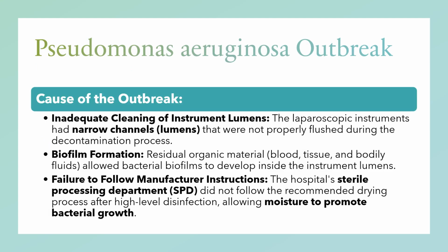All right, so the causes of the outbreak were inadequate cleaning of the instrument lumens, so the internal component. Those narrow channels were not properly flushed during the decontamination process, which means previous patients' bacteria, bodily fluids, and tissue were still in that inner lumen portion.